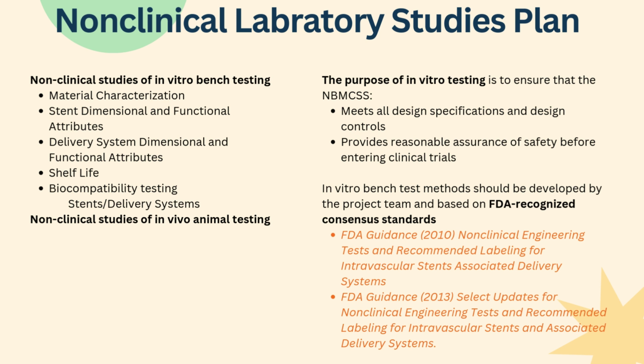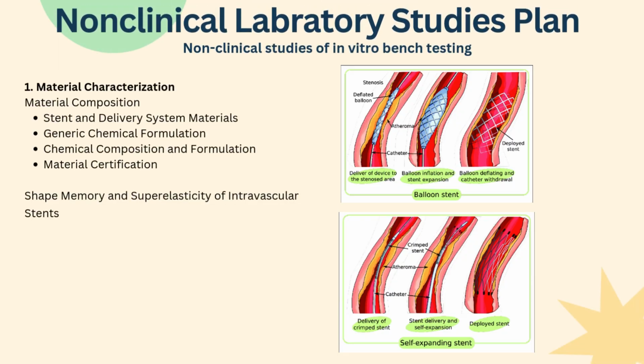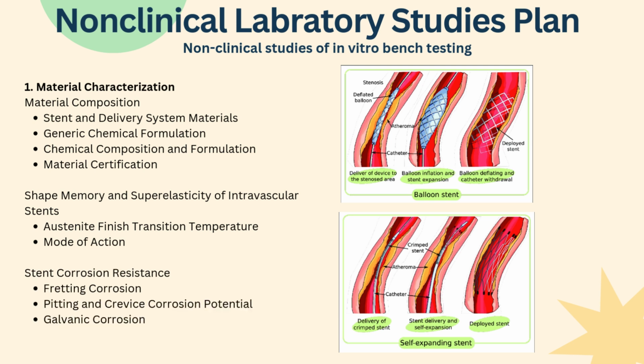Our in vitro bench testing methods will be developed by the project team and based on the FDA guidance listed on the slides, to ensure that the test results are valid and acceptable for regulatory review. Next, because the device incorporates a novel material, the material characterization is particularly important. These evaluations include a comprehensive assessment of the material's composition, shape memory, and the superelasticity of intravascular stents, and corrosion resistance. These steps are critical to ensure that the material will not degrade or release harmful byproducts once implanted.